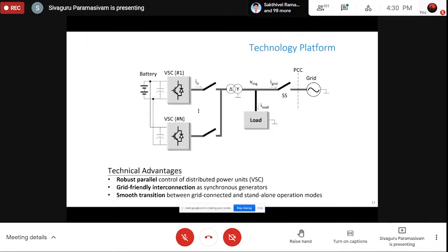So when there is a complete grid outage, we open the grid switch and form a microgrid, and we activate all the components and equipment within our renewable assets. That's where the complex power electronic control system comes into play, and that's what we call VSG, virtual synchronous generator. It will be able to maintain the voltage when there is no grid. The battery inverter will be able to maintain the voltage at 230 or 440 for single phase and three phase respectively, and maintain the frequency at 50 Hertz, and only the current to the load will depend upon our source.